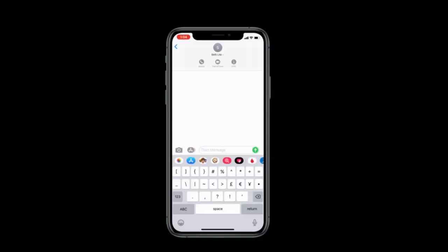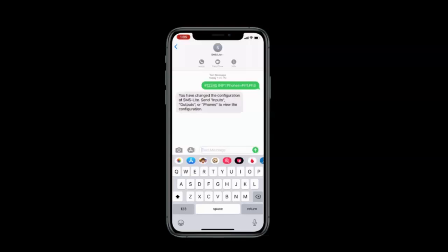You can also choose which configured phone numbers will receive notifications from each input and which configured phone numbers have permission to control each output. For example, to configure input 1, instead of name in the item position, swap in phones and then equal to the phones that you want to ring the alarms. It's important to note that the numbers step in numerical order. If you were to attempt to program phone 4, phone 2 and phone 3, the configuration text would be accepted, but the escalation order would be phone 2, phone 3, and then phone 4.